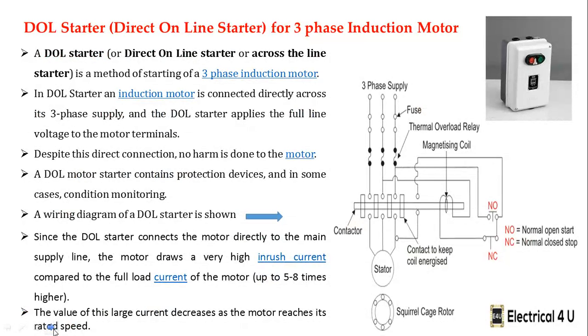Next is the starter which is used to start the three-phase induction motor in a safe manner. That is nothing but the DOL starter, that is direct online starter. So the DOL starter is a method of starting a three-phase induction motor. In a DOL starter, an induction motor is connected directly across its three-phase supply. Here, the three-phase supply is given as shown in the diagram, and you can connect the DOL starter directly to this three-phase supply, and the DOL starter applies the full line voltage to the motor terminal.